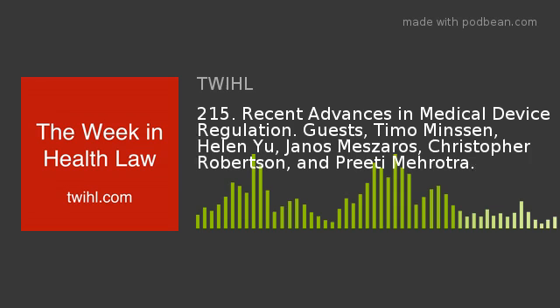Regulation, which was supposed to come into force in May 2020, was supposed to replace the medical devices directive. Now, because of the pandemic, the implementation of the MDR has been postponed for a year. As a regulation, the MDR is considered an enforceable law in all member states of the EU, and its intention is to improve the safety of medical devices.